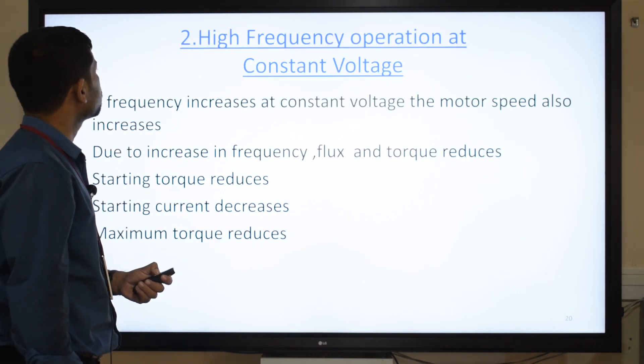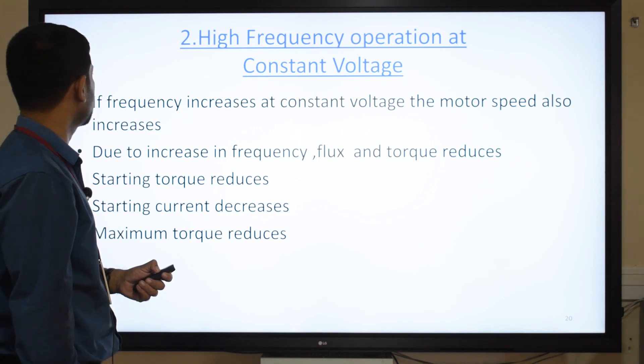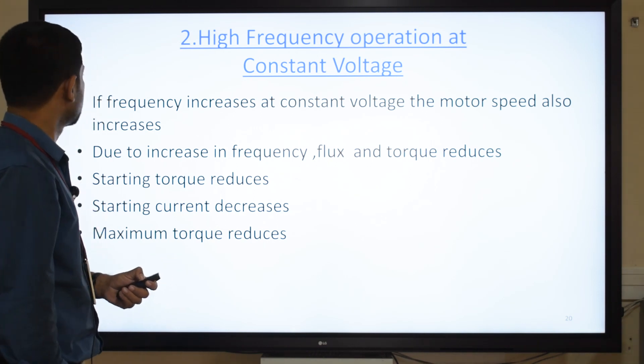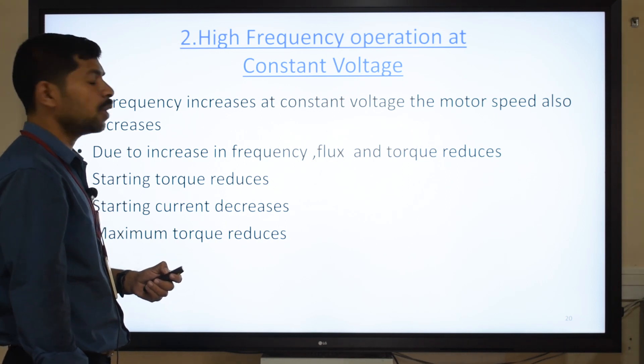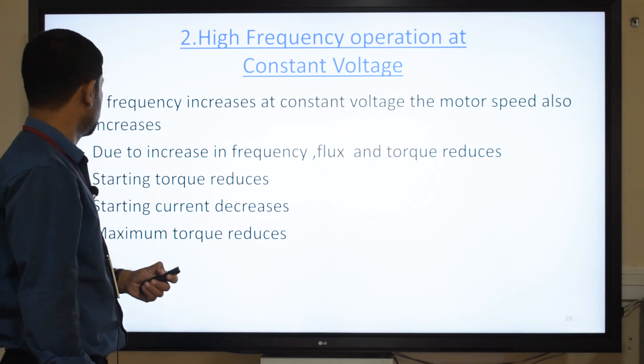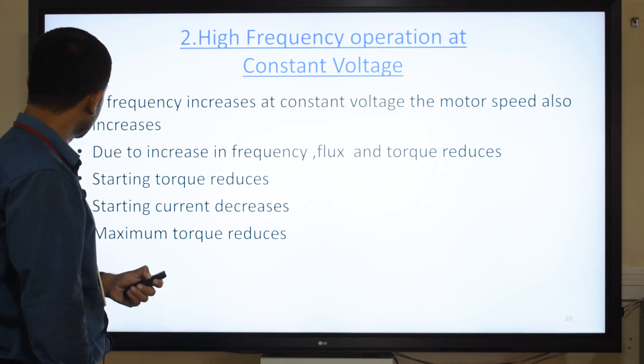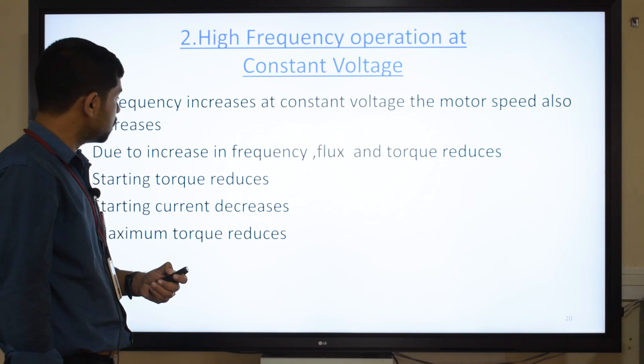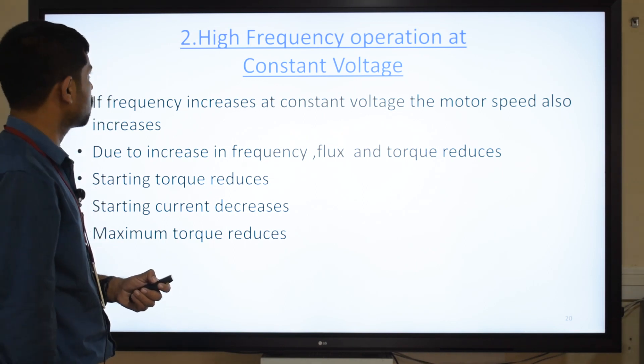The second case is high frequency operation at constant voltage. Here frequency is increased. If frequency increases at constant voltage, motor speed also increases. Due to the increase in frequency, flux and torque reduce, starting torque reduces, starting current decreases, and maximum torque reduces.